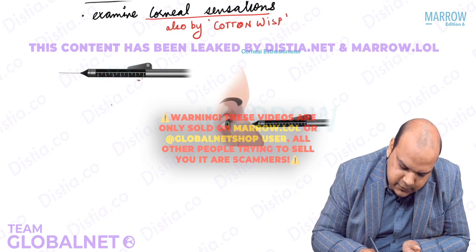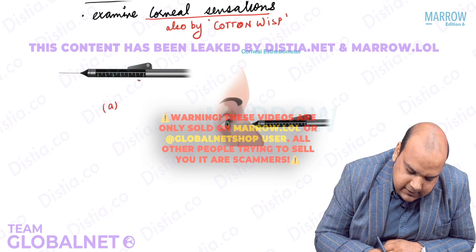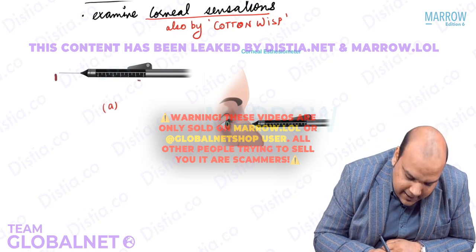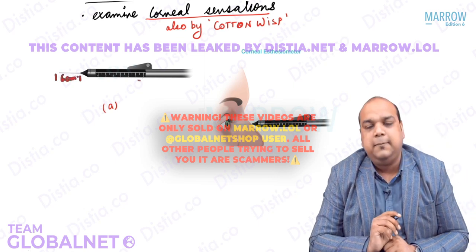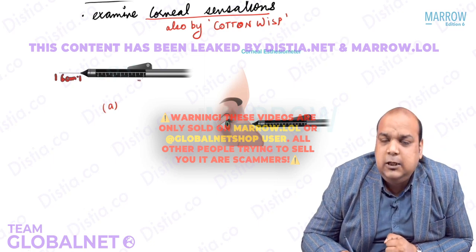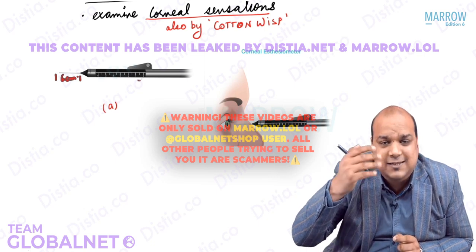Yes. So this instrument, image A here, is a pen-like instrument with a thin filament which comes out from it. The maximum length of this thin filament is 6 centimeters. The filament will touch the cornea of the patient. We open it completely first to 6 centimeters. We touch the cornea and see whether the patient is able to feel the sensation or not.